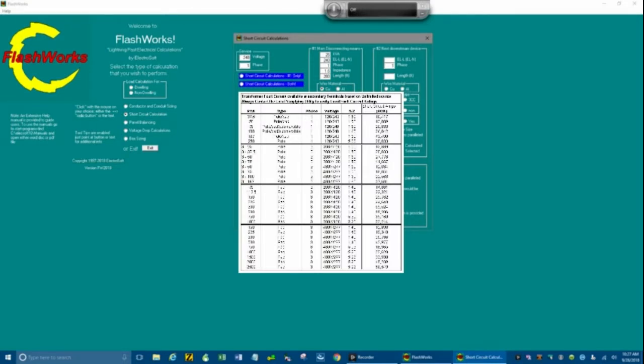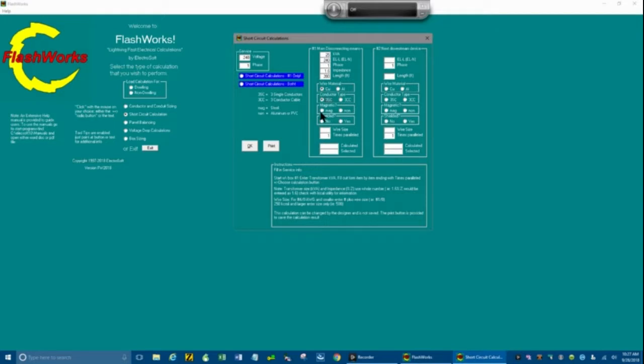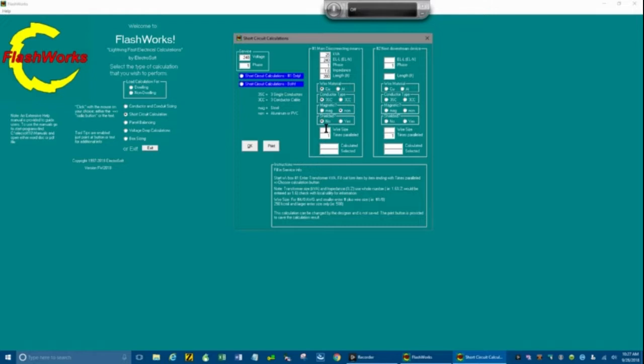The wire material is copper. It's three single conductors in conduit. Notice these acronyms are over here. Is it in steel pipe or PVC? Let's say it's in PVC. Is it shielded or not? Let's say no. For the wire size in this particular one, let's use 2 aught. Put in the pound sign and then 2 slash 0 for 2 aught.